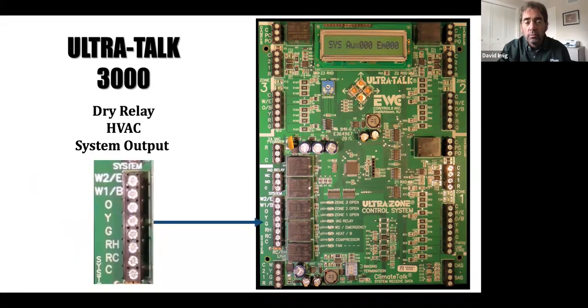Above that is a dry relay output terminal strip. This has a couple of different options. One, it can be used for IEQ, which I'll show you here in a bit. The other is this panel could be used in an emergency. If you didn't have a panel available, this could be used in a 24-volt non-communicating application. In a non-communicating application, it becomes a 2-stage heat, 1-stage cool zone panel. Again, only for emergency needs would I use this panel in a non-communicating application.